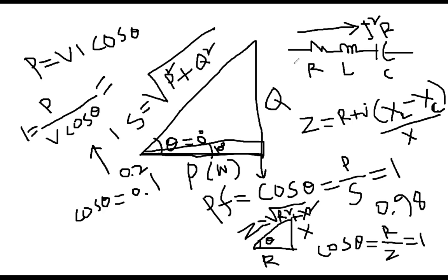On the other hand, if your I value is small, there will not be much difference between the voltage here and here. So if your power factor value is low, in other words your Q value is high, then you will get higher current. That will cause higher loss, higher voltage drop, and much more loss means the system will be less efficient.